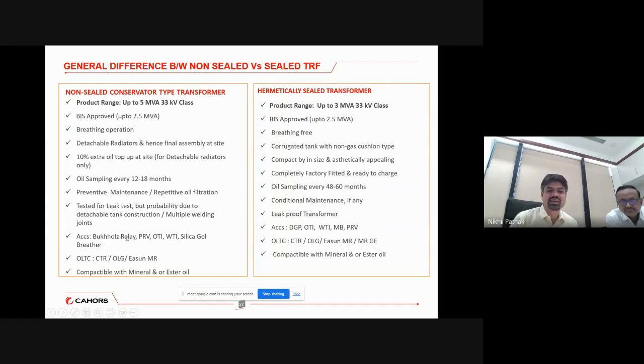And then accessories are there when it comes to the conservator. The Buchholz relay comes, the MOG comes, PRV comes, OTI, WTI, and silica gel breather comes. However, in a sealed type of transformer, since there is no conservator, the Buchholz relay is eliminated. So normally MOG is also eliminated. Then the silica gel breather is also eliminated, and we are giving an integrated device which is nothing but the detection of gas and pressure, a DGP relay. It is the combined approach for understanding slow developing faults, as with the Buchholz relay, gas-based operation, and abnormality in the pressure of the transformer.